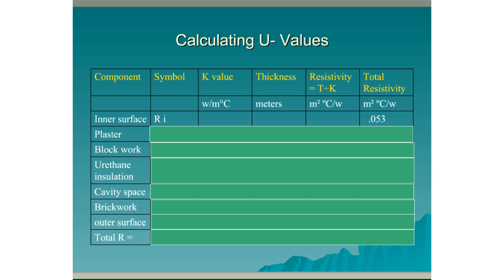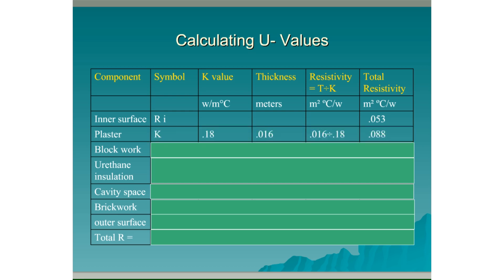The inner surface (symbol Ri) has a resistivity of 0.053, entered directly into the totals column. The plaster has K value 0.18 and thickness 0.016 m (16 mm): 0.016 ÷ 0.18 = 0.088. The block work has K value 1.33 and thickness 0.102 m (102 mm): 0.102 ÷ 1.33 = 0.076.